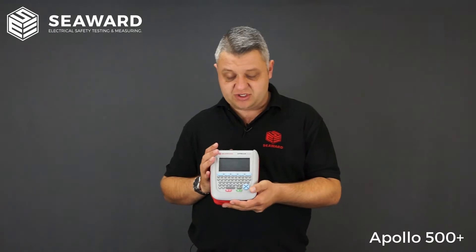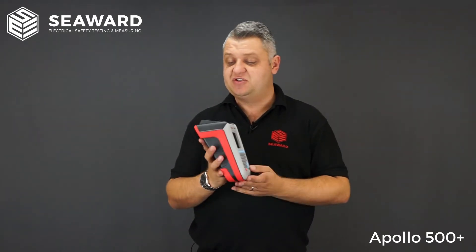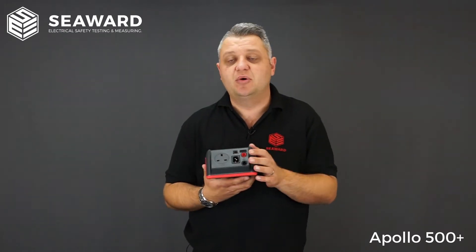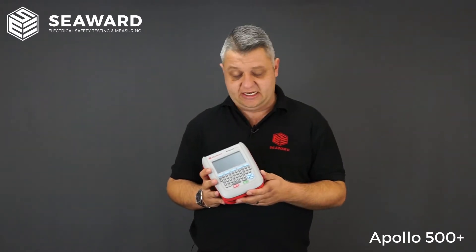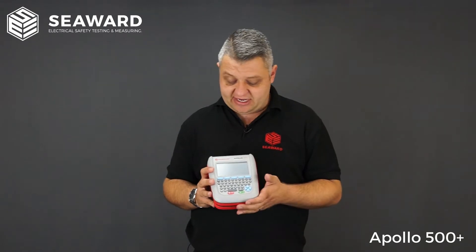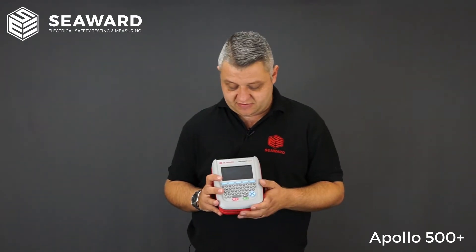The 500 covers all tests required in the IET fourth edition code of practice, and also has the facility to test fixed appliances using point-to-point testing methods. It has a 250 volt insulation test for anything sensitive or any IT equipment you may be testing, including surge protective extension leads. The RCD test is also built in, so if you have any plug-in RCDs or RCD protective extension leads, the facility to test those is included.